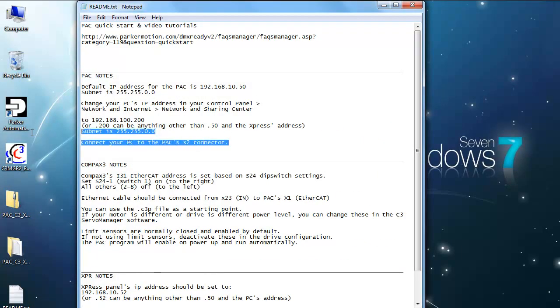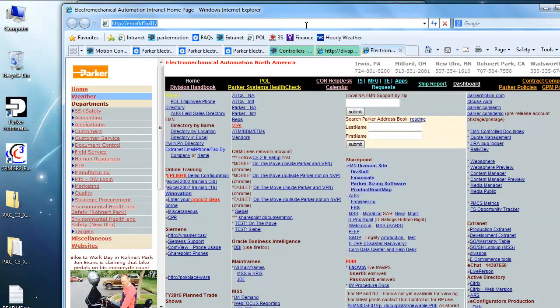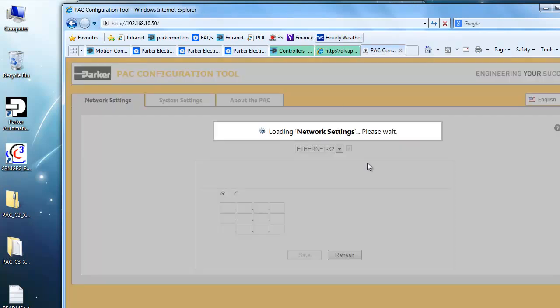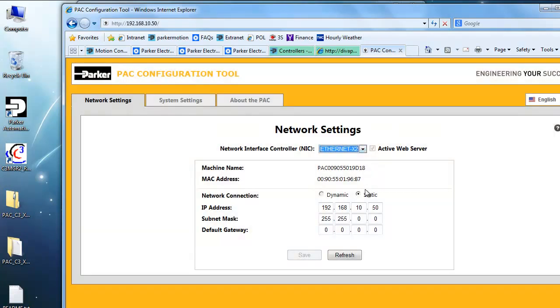You need to connect your PC to the PAC's X2 connector. The X3 is set to UDP instead of TCP, so you need to use the X2 first to establish communication. If you want to verify, open up an Internet Explorer, go to 192.168.10.50, and you can see the X2 — that's the connector you're actually connected to. That's the machine name, and you can see that it's static.